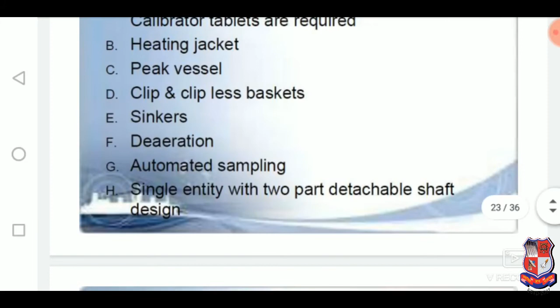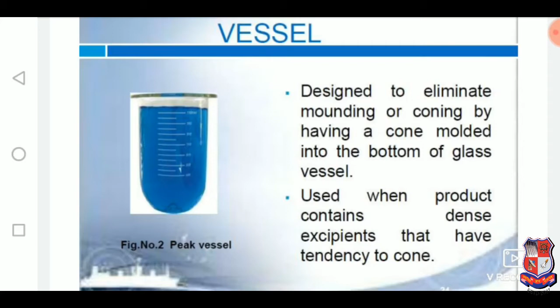So first one is the peak vessel, designed to eliminate the mounding or coning by having a cone molded into the bottom of the glass vessel. Used when product contains dense excipients that have a tendency to cone. So peak vessel is generally used for that dense excipient containing product, because if we use a normal dissolution bowl, then the convection flows are there, and to avoid that we have to use that peak vessel.